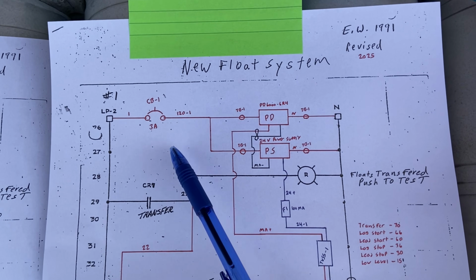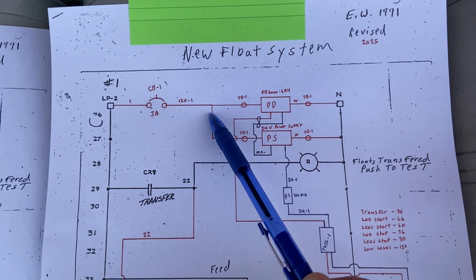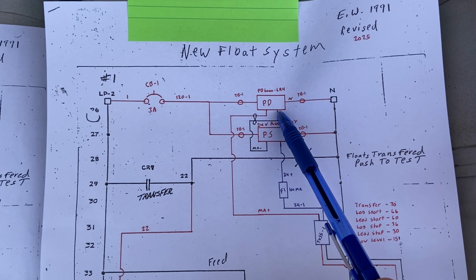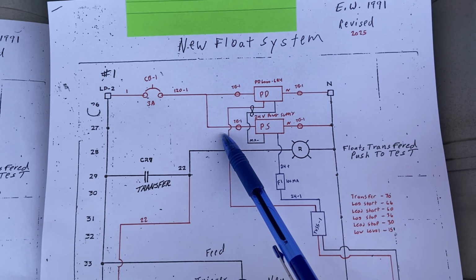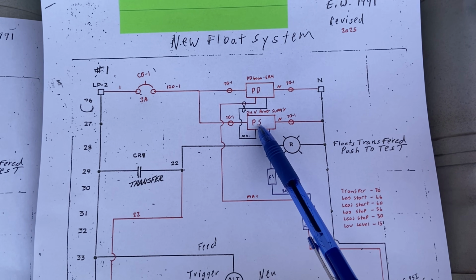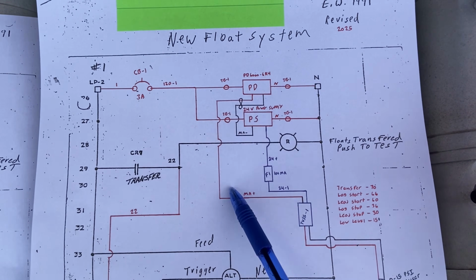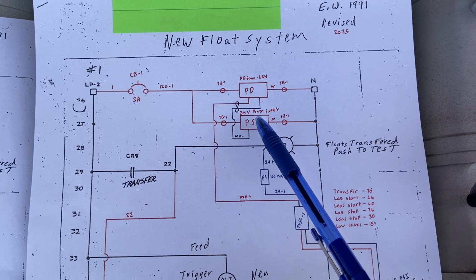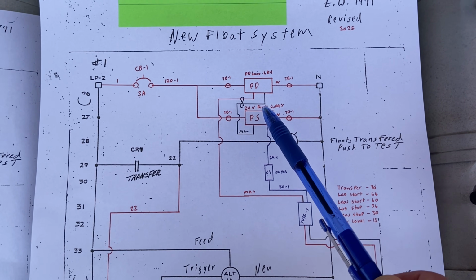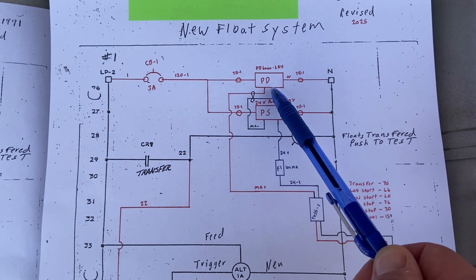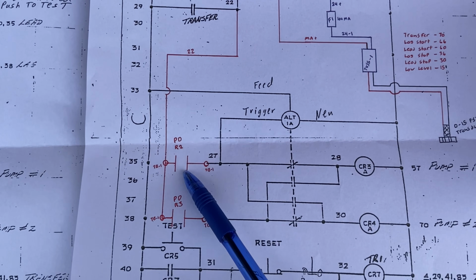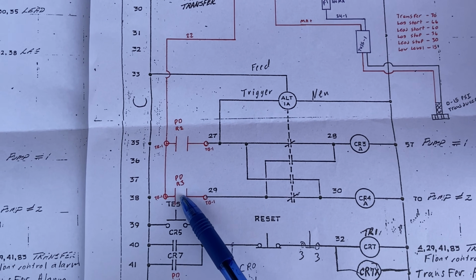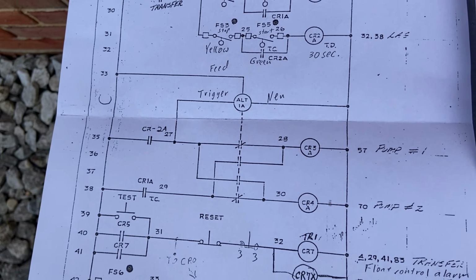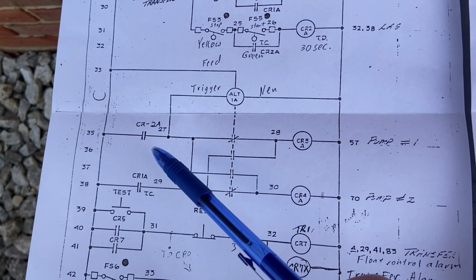As you can see, I broke out the ruler for this one. Definitely could have been better, but most people wouldn't have done this at all, so it's better than that. So I added a 3 amp breaker on the 120 side, and that just kind of isolates all the new wiring, and it feeds the display and the power supply. This is obviously a 120 volt display, but you can get them in different voltages. And from the display, here is 2 of the relays, the lead and the lag relay from the display, and that replaced our CR2A and CR1A.